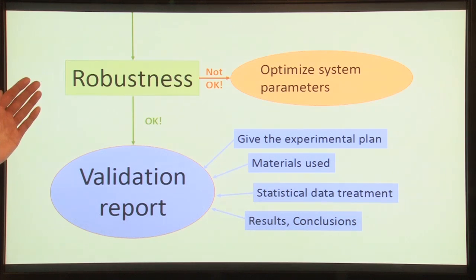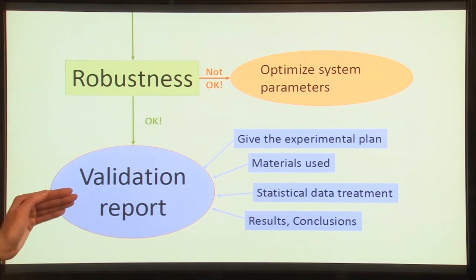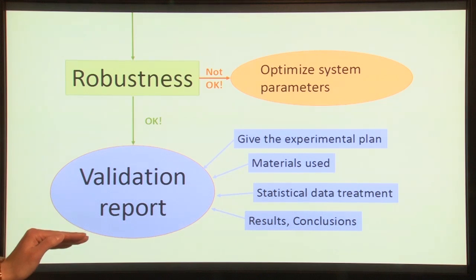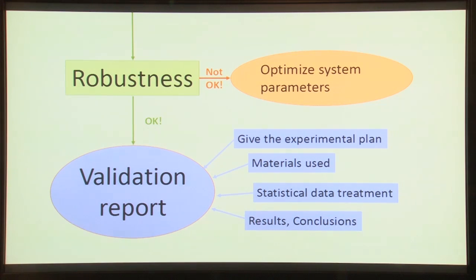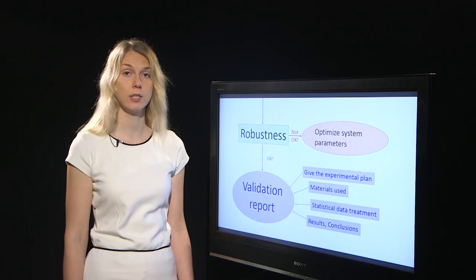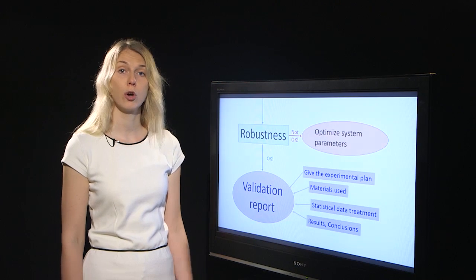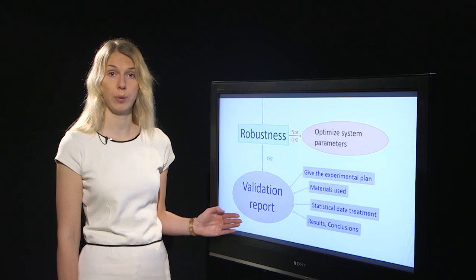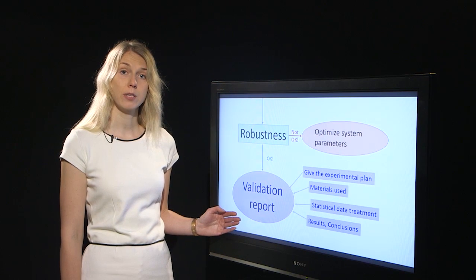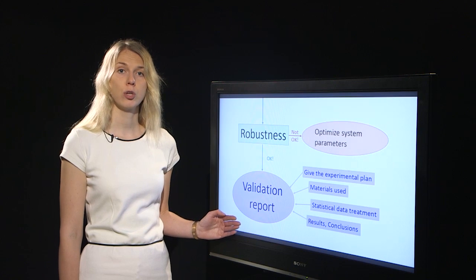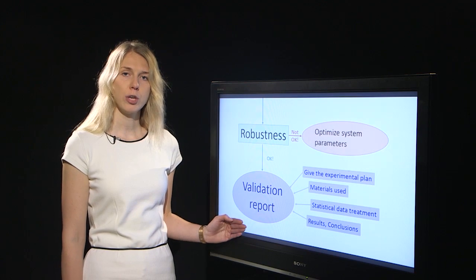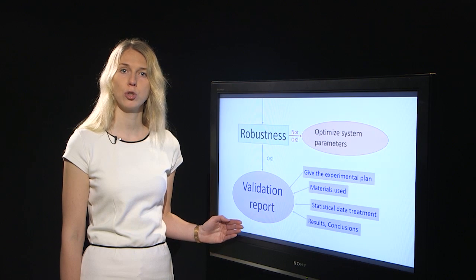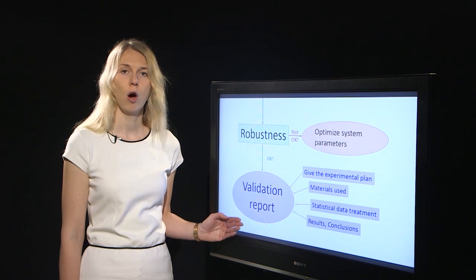If you have also found acceptable robustness, then you should conduct a validation report. This means writing down what experiments you carried out, what results you obtained, what statistical tests you did, and what you could conclude from these results. However, validation does not stop here. For the parameters that are most critical to your method, you should continue monitoring these parameters also during the routine use of your method.